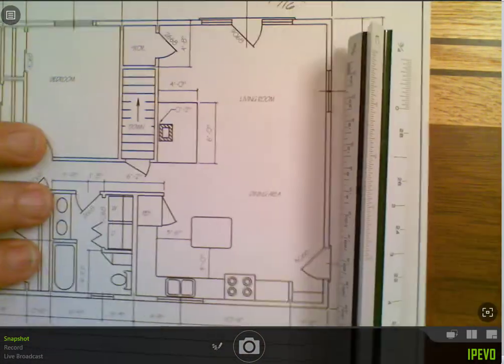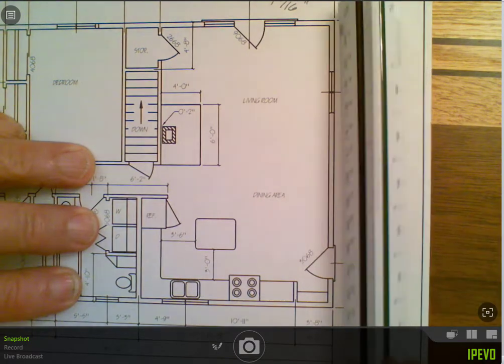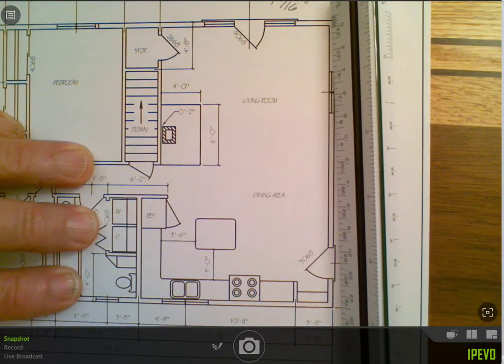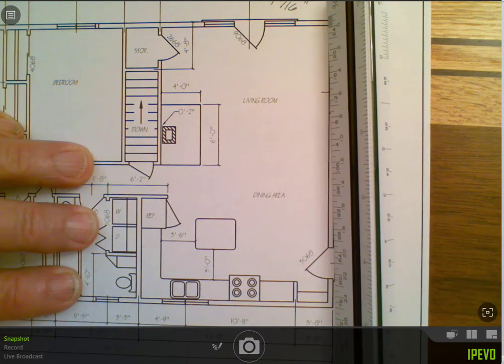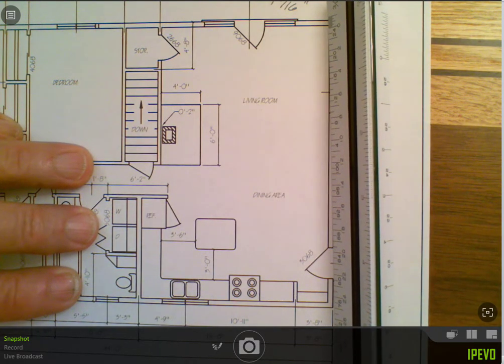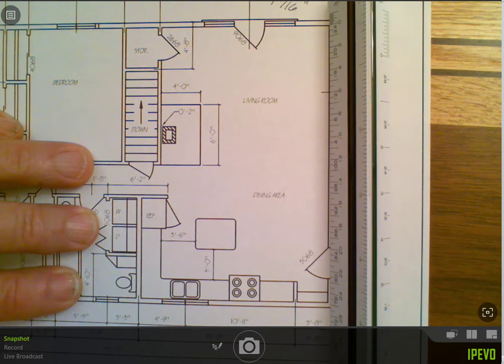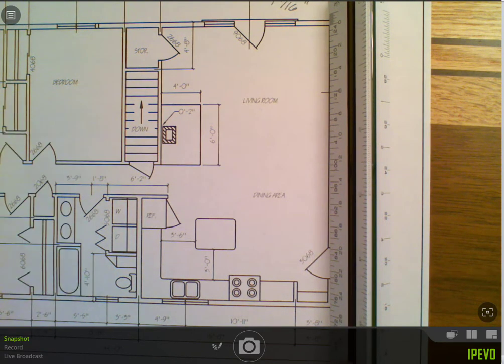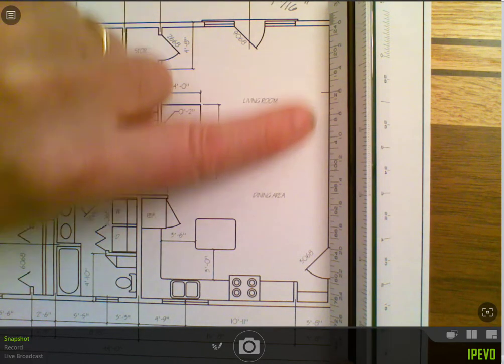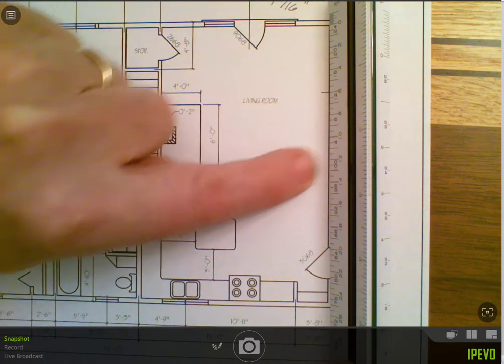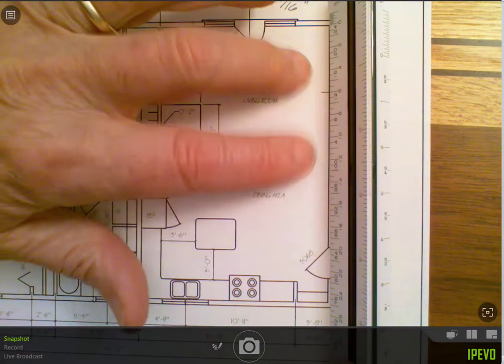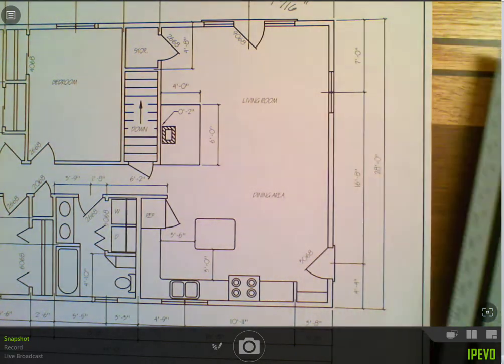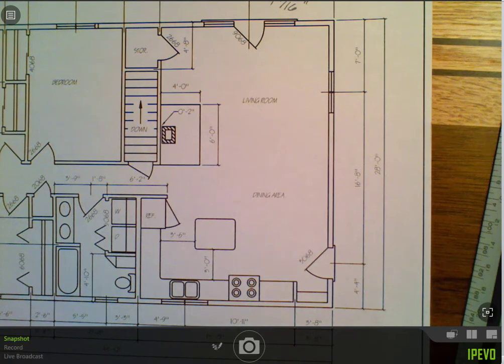I want to make sure I put receptacles close enough together. If I measure from here to here, and say I want to make sure that no point along the wall is further than six feet away, I've got my six feet, I can measure out to twelve, make sure receptacles are less than twelve feet apart along that wall. Now I know I'm meeting the requirements of the National Electrical Code.